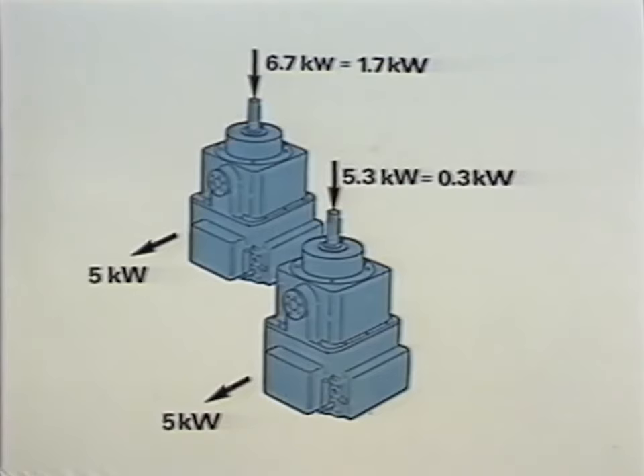Let's compare the two shown. They both generate the same capacity, namely 5 kilowatt. The pump at the top has a poor level of efficiency and therefore demands an installed capacity of 6.7 kilowatt in order to generate 5 kilowatt. The energy loss here is therefore 1.7 kilowatt.